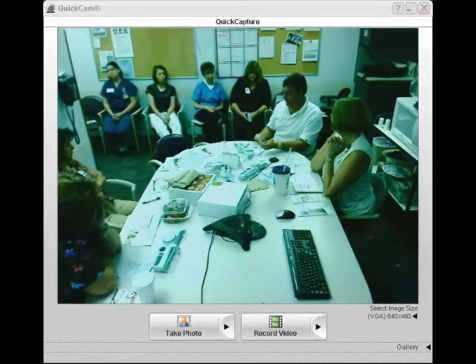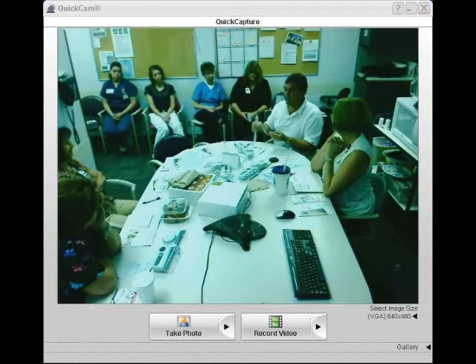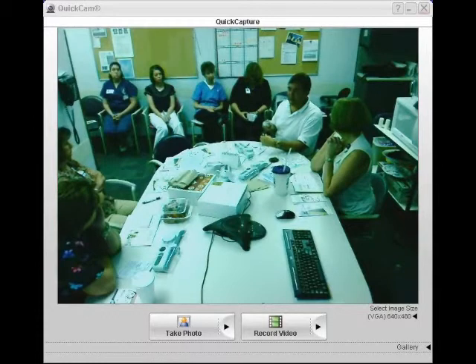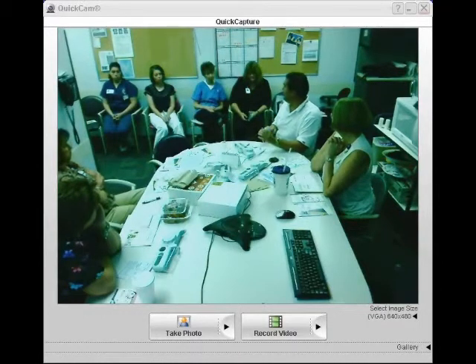It's kind of hard to explain over the phone, but David's seen me do this enough times that he can probably show you exactly what I mean. Yes, I'm doing it as we speak. It's not too complicated. The one piece that she mentioned is this is the flow rate tubing set. They come in different lengths. So the slower the infusion is going to take place, the longer the tubing piece is going to be. The faster will be a shorter piece. So they do come in different lengths, and that's what sets the flow rate.